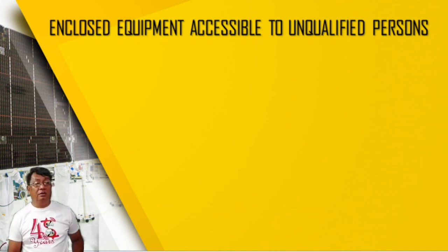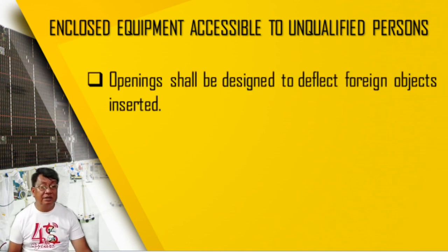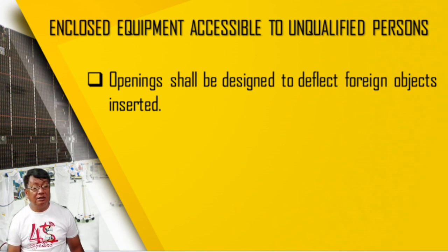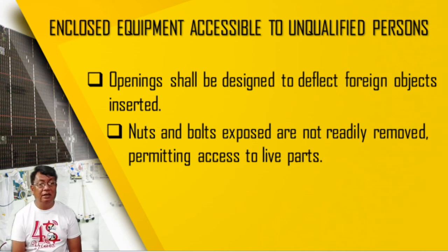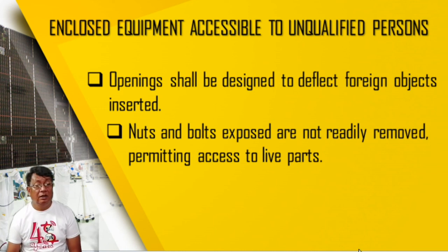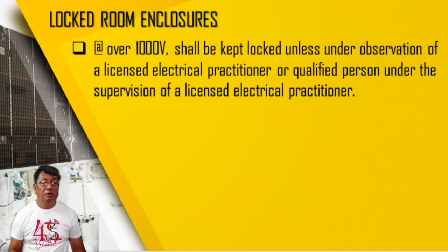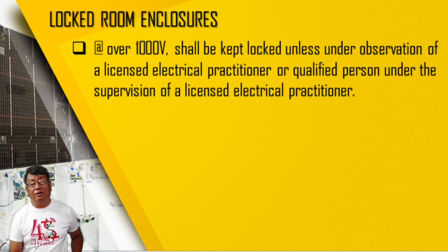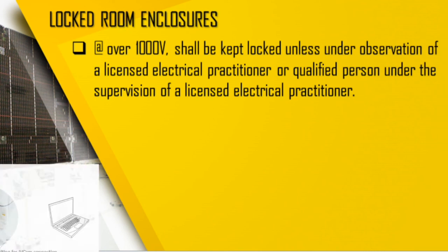We have enclosed equipment accessible to unqualified persons. So, who are these, no? Openings shall be designed to deflect foreign objects inserted. So nuts and bolts exposed are not readily removed, permitting access to live parts. Okay. So locked enclosures over 1000 volts shall be kept locked unless under the observation of a licensed electrical engineer or qualified person, or under the supervision of a licensed electrical engineer. So those are some violations if we can follow these circuits.